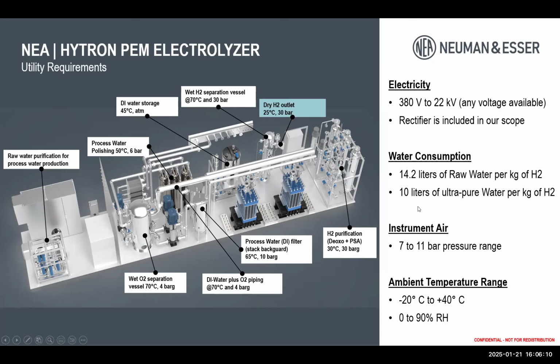In terms of water consumption, you need about 14.2 liters of raw water per kilogram of hydrogen. The system will produce around 10 liters of ultra pure water per kilogram of hydrogen that will meet the stack requirements, primarily for conductivity. A lot of that water is circulating through the stack to cool it down, as you probably know, because it is an electrochemical reaction that generates heat. Most of this ultra pure water is just cooling down the stack, and part of the water will actually be split into hydrogen and oxygen.